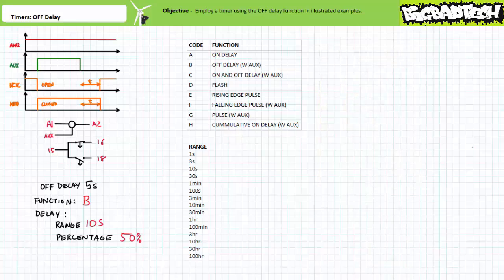Troubleshooters take note. A multifunction timer executing the right function at the wrong time needs to have the delay adjusted. In contrast, a multifunction timer executing the wrong function at the right time needs to have the function adjusted. I'd like to say the misinterpretation of functions is a rare occurrence, but it isn't, and you need to be aware of this possibility.